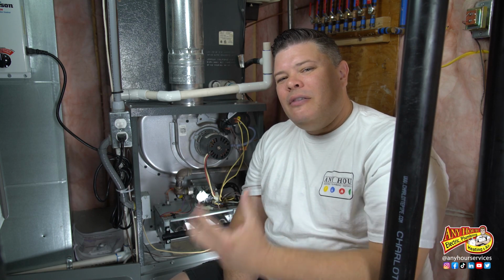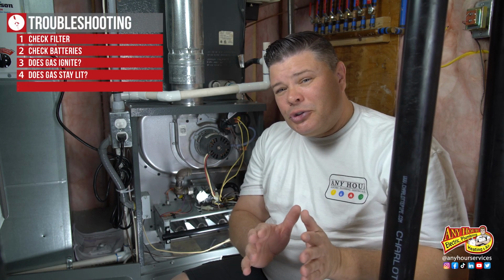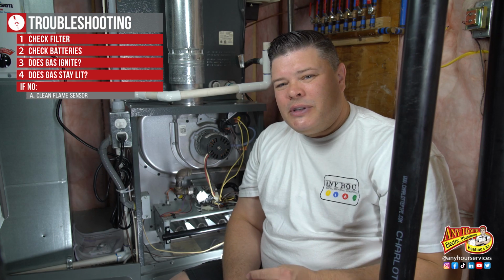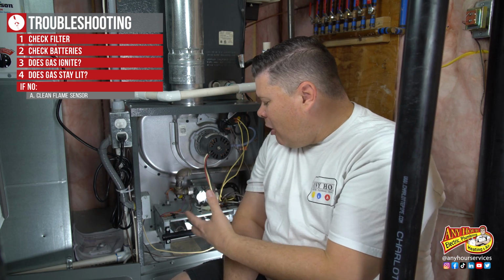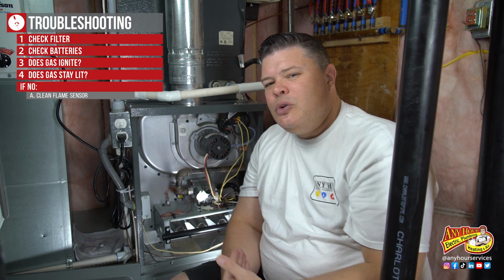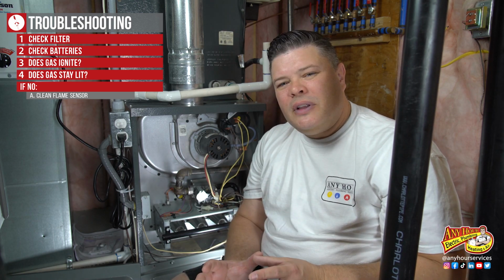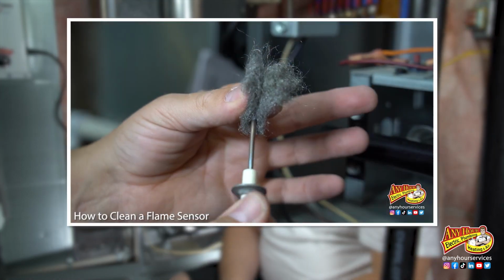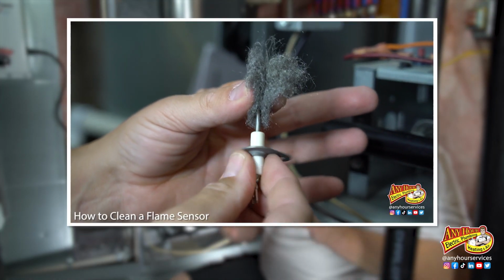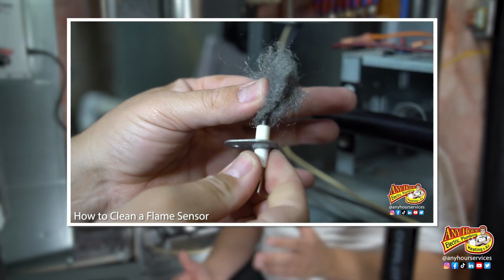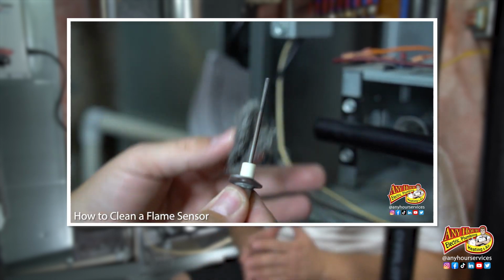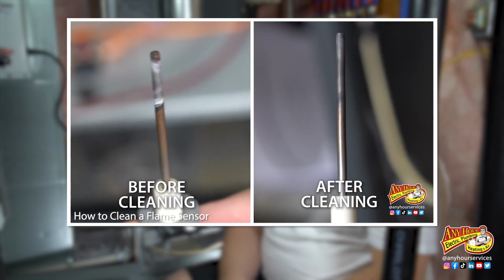The easiest and most basic thing for homeowners to try and fix this issue, if you're comfortable trying it, is to actually clean the flame sensor. Now, not all flame sensors are as easy to get to as mine, but if you can locate where the flame sensor is and get it out, cleaning it is pretty straightforward. You can actually check out a video that we made on how to clean your flame sensor. All you really need is some steel wool to do that. We put a link down in the description if you'd like to see that.